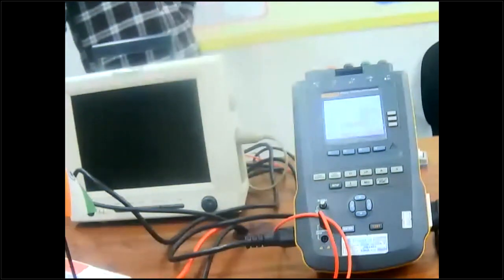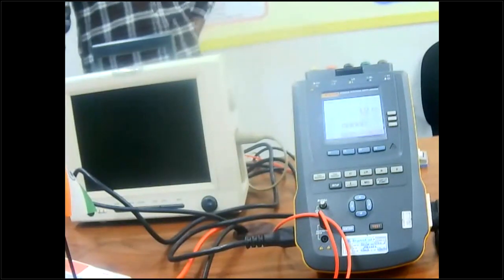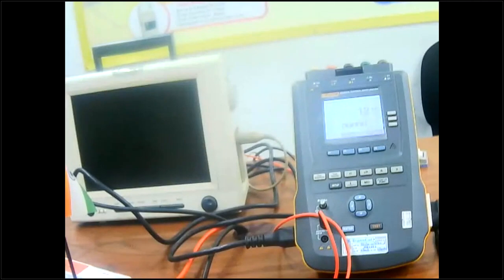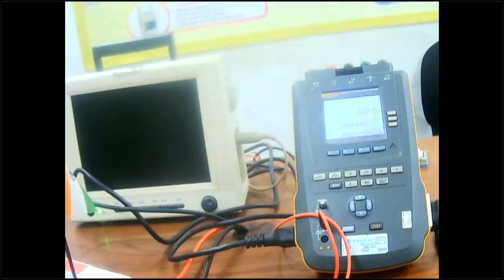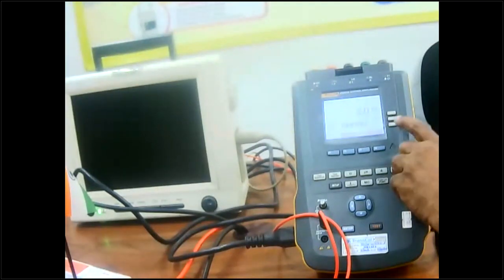Other than that, we can test by doing AC only, or AC plus DC, or only DC. We can do all these tests. Next, we can test a single fault condition. For that, we press the polarity. This is normal polarity. You are going to see 2 microamps. Different equipment may show different readings, but this is what it is showing.